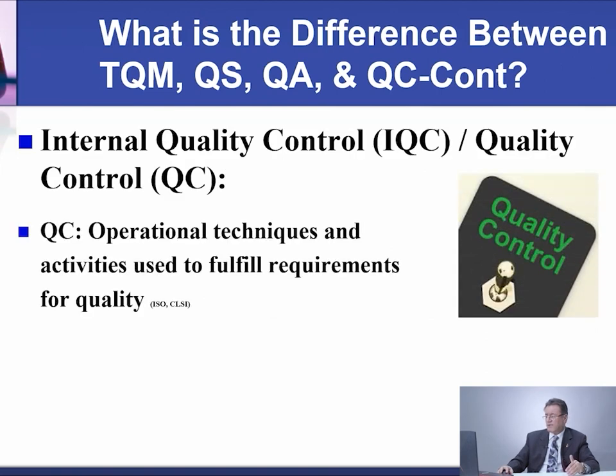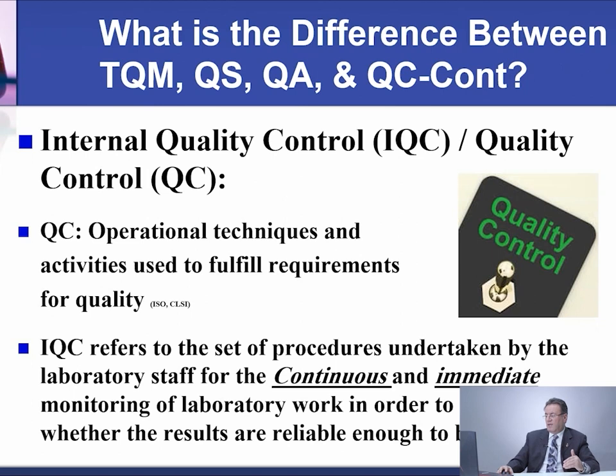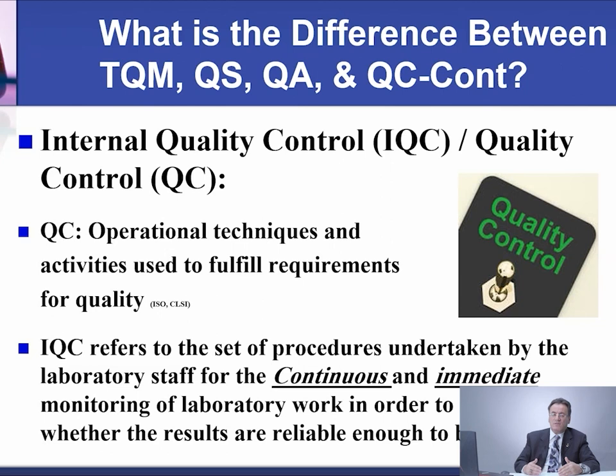IQC, on the other hand, refers to operational techniques and activities used to fulfill requirements for quality. It refers to the set of procedures undertaken by laboratory staff for continuous and immediate monitoring of laboratory work in order to decide whether the results are reliable enough to be released. When running QC, the purpose is to tell you whether your instrument and kit are functioning correctly — if QC is within range, you can feel comfortable reporting patient results; if QC is out, you cannot report patient results and you need to correct the situation.